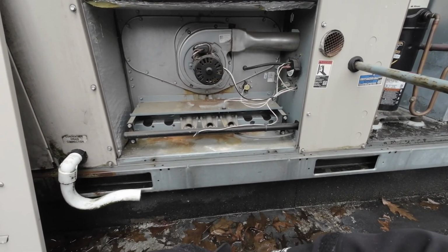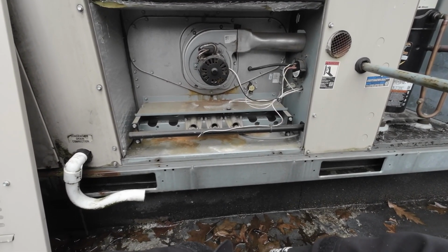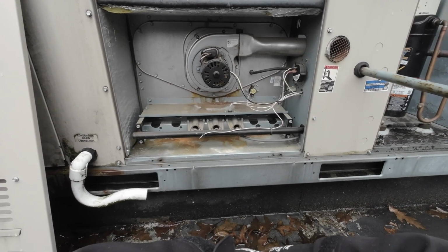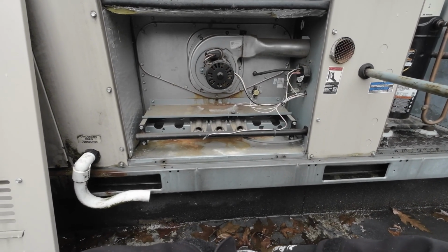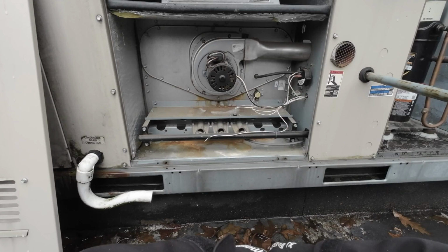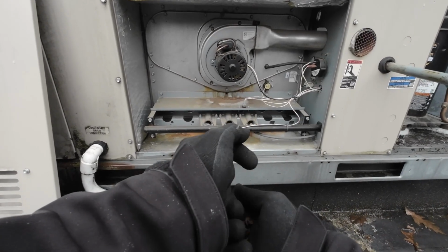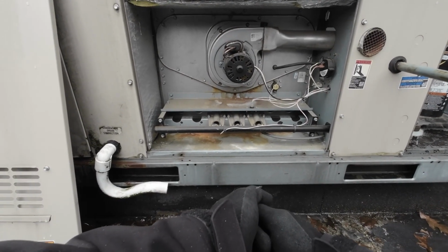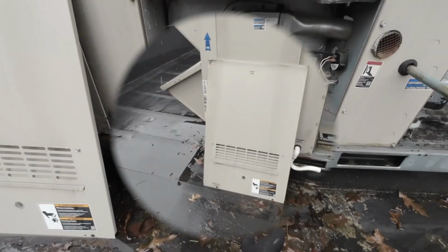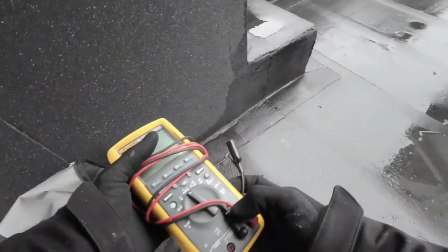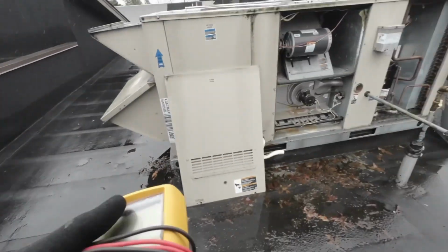So they said they got no heat here. Yeah, you can hear it - the pressure switch is not closing because of it. Let's grab the meter and see if that pressure switch is closing. No, there it is, pressure switch closed.